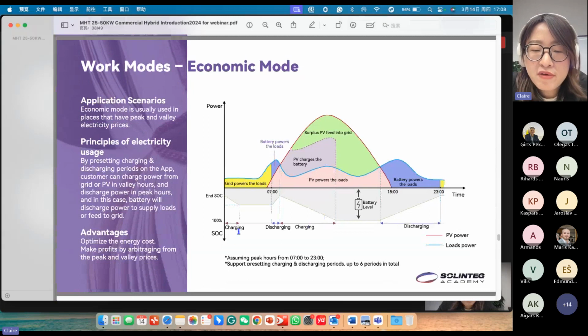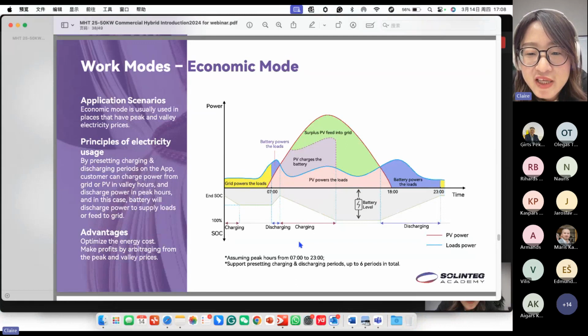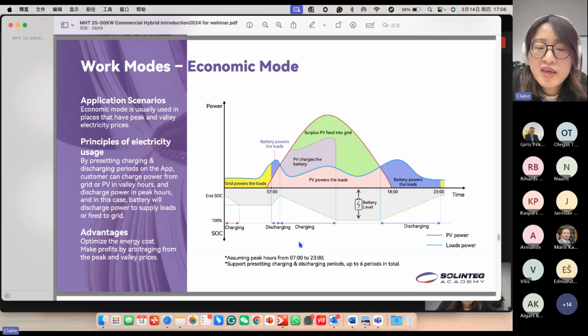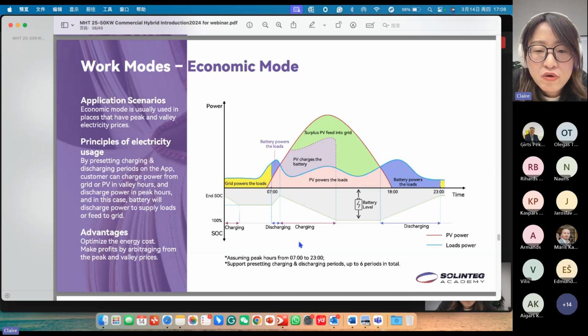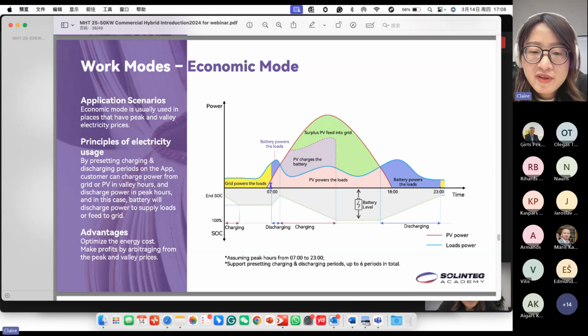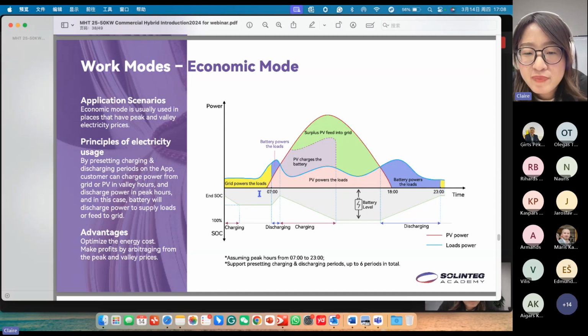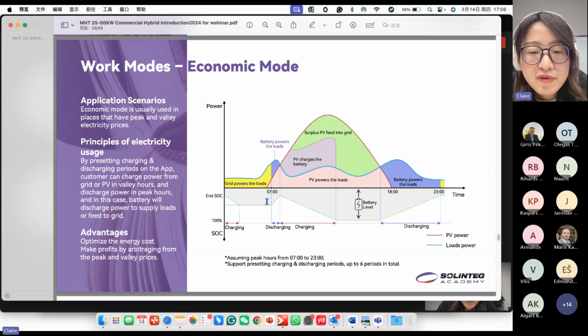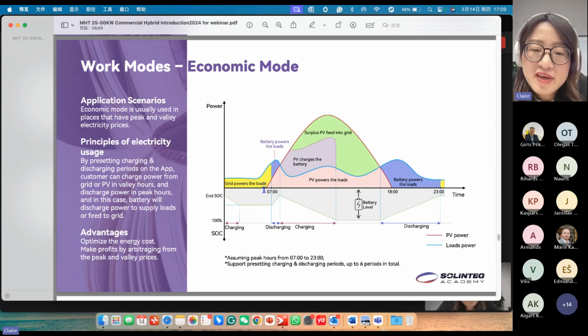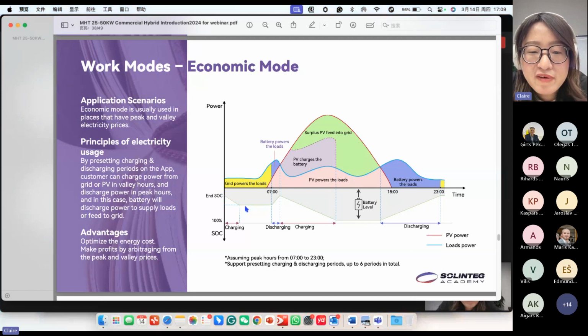And this economic mode is quite useful for countries that have peak and valley prices. Also in some countries they use dynamic prices. We can set up to 6 periods of charging and discharging groups. Here we can see in the morning, we get up and are using some load, so the power in the battery may have been used up or reached the SOC protection value. So the loads at this time will be supplied by the grid, and there's still some power in the battery, so the battery level is a little bit higher than the SOC value.